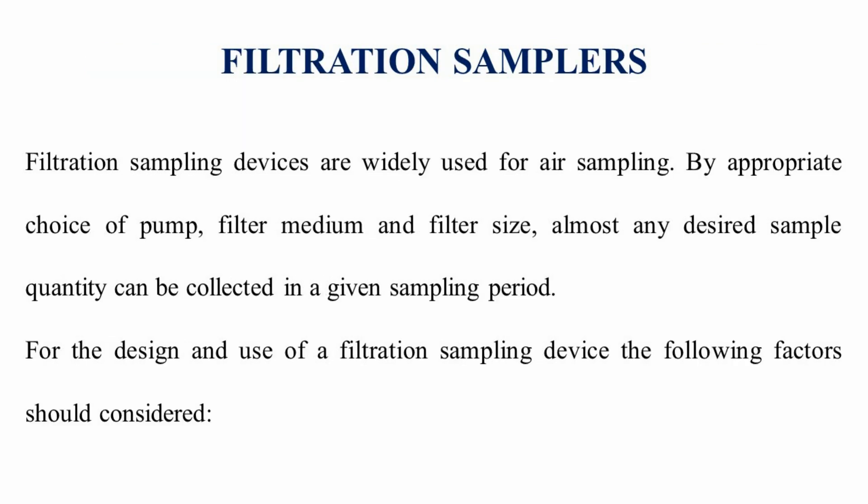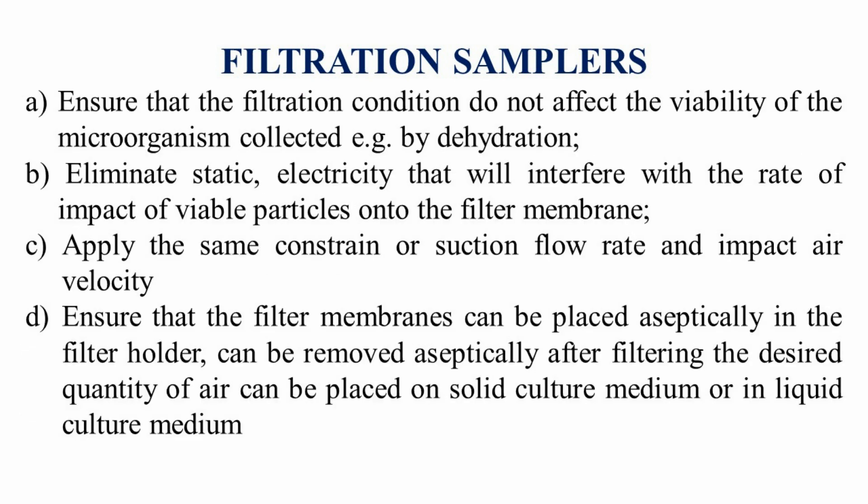Filtration sampling. Filtration sampling devices are widely used for air sampling. By appropriate choice of pump, filter medium, and filter size, almost any desired sample quantity can be collected in a given sampling period. For the design and use of a filtration sampling device, the following factors should be considered. Factor A: ensure that the filtration conditions do not affect the viability of the microorganisms collected, for example by dehydration. The filtration conditions should not cause the medium to dry while sampling, and the filter should not show adverse effects on the growth of viable particles.